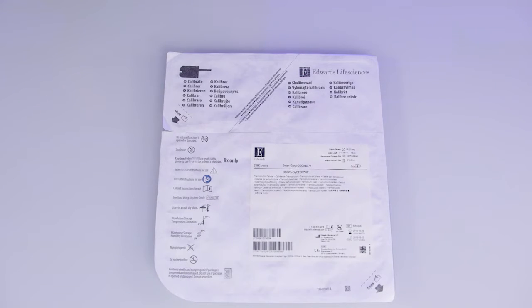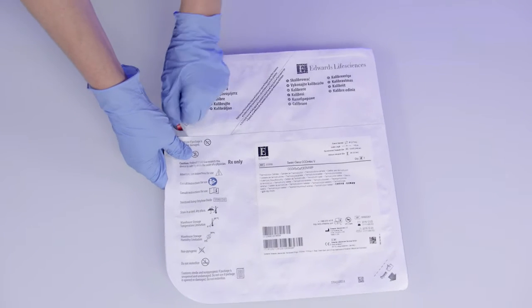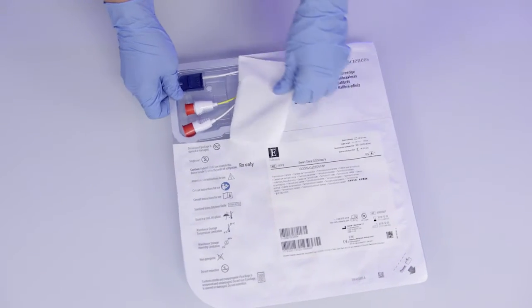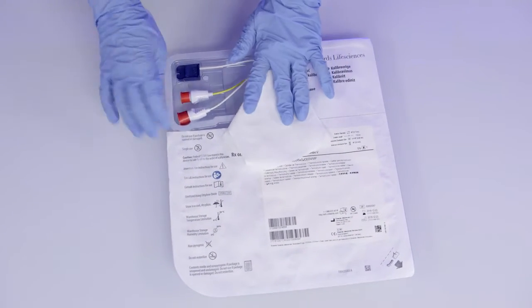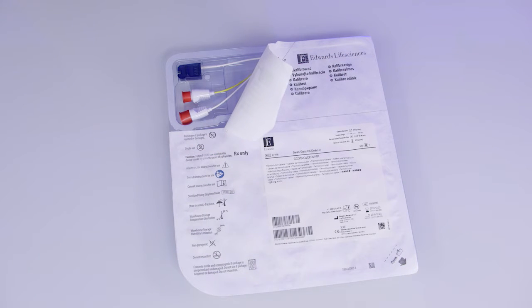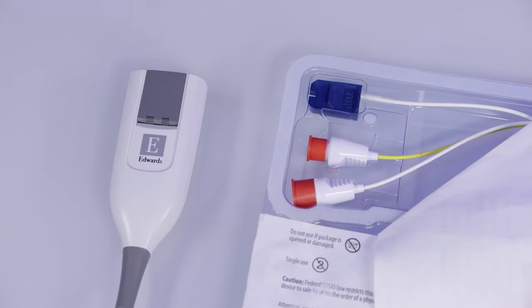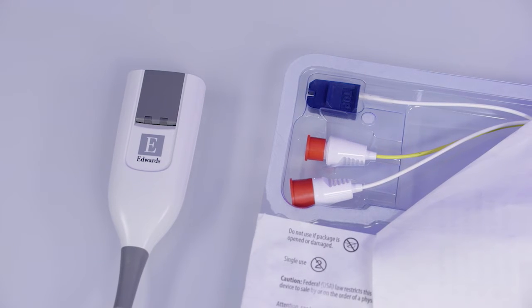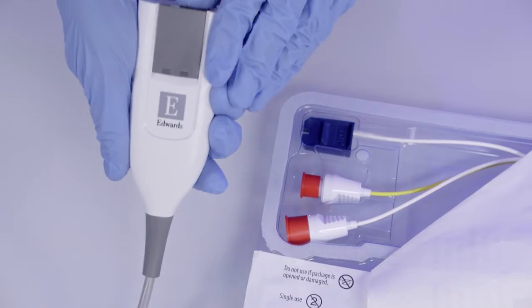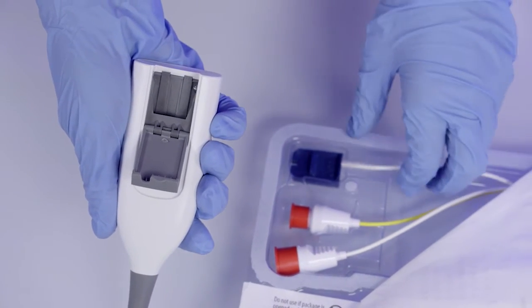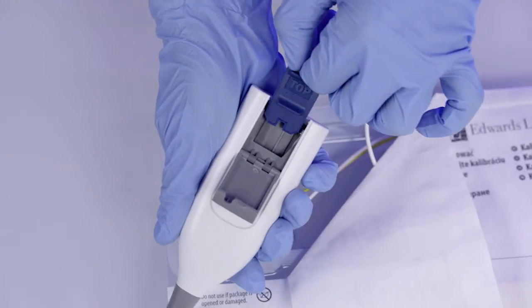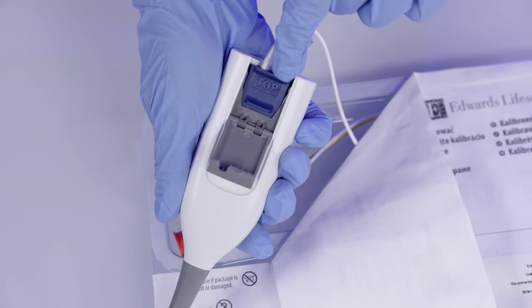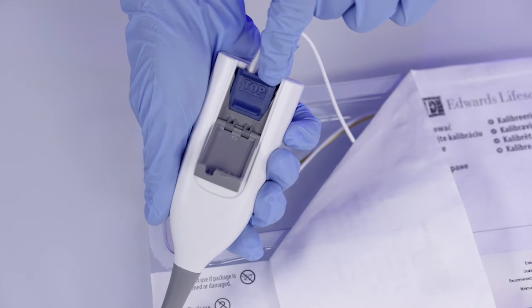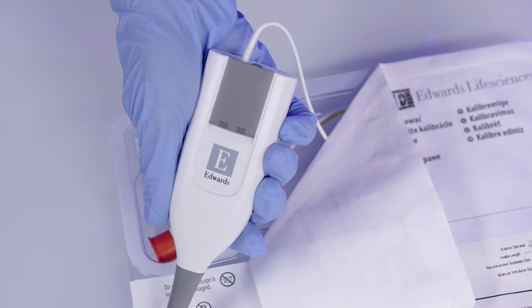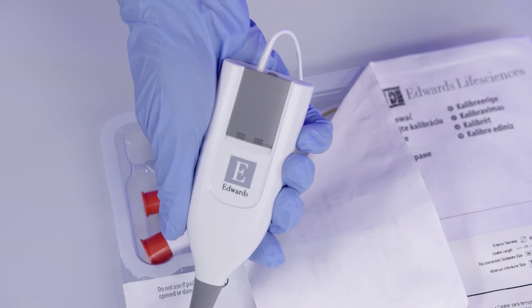To perform in vitro calibration, only open the perforation tab on the catheter packaging. This will expose the optical module connector of the catheter and will leave the distal part of the catheter sterile. Connect the optical module connector on the catheter to the Edwards Oximetry Smart Cable by lifting the lid on the HemoSphere oximetry cable and inserting the optical module connector. Make sure you can see the word TOP on the tab. Close the lid of the HemoSphere oximetry cable over the optical module connector until it snaps into place.